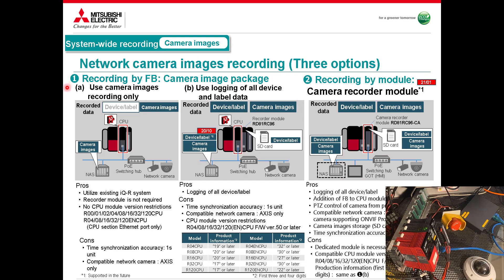The piece we're going to look at is scenario 1a. We also have 1b and option 2. This scenario is network camera recording using an Axis camera. We have a standard CPU connected via the front port to a hub and switch going out to the Axis camera. That camera can store data internally on an SD card or via a network share — in this case, a shared folder on our PC. The CPU sets the camera's time and tells the camera when to record images and push them to the shared server. The CPU also does logging, and the video file and logging file will be synced.